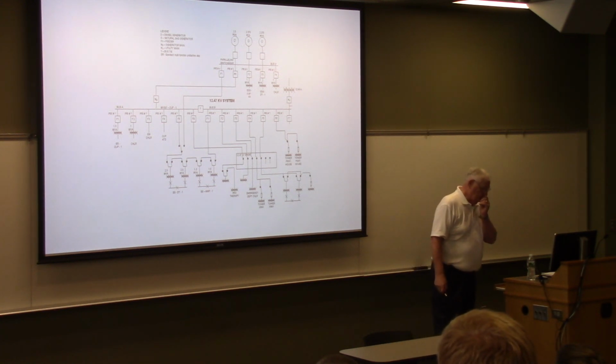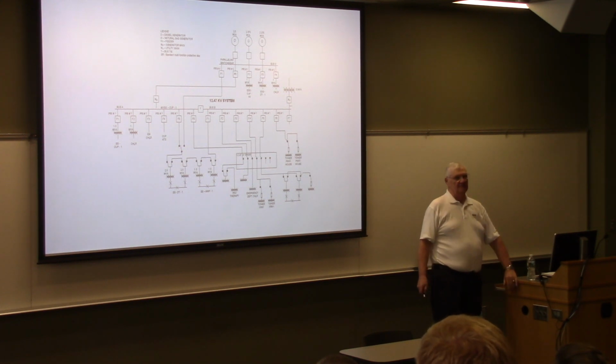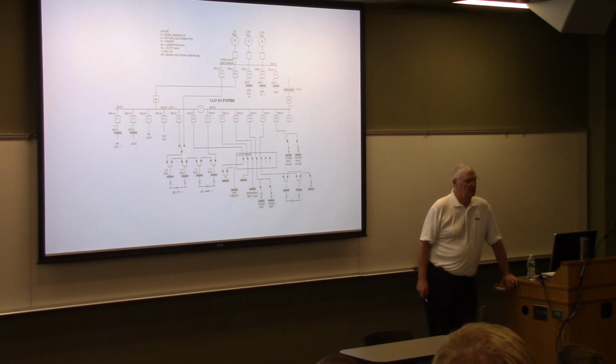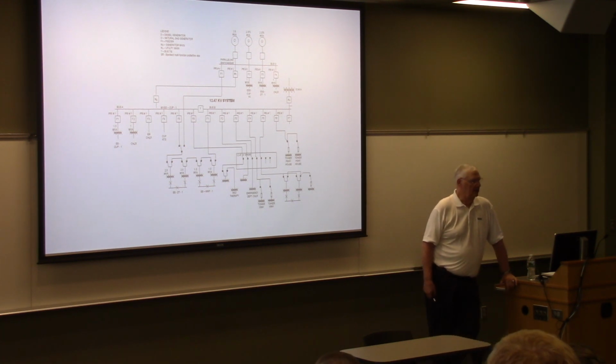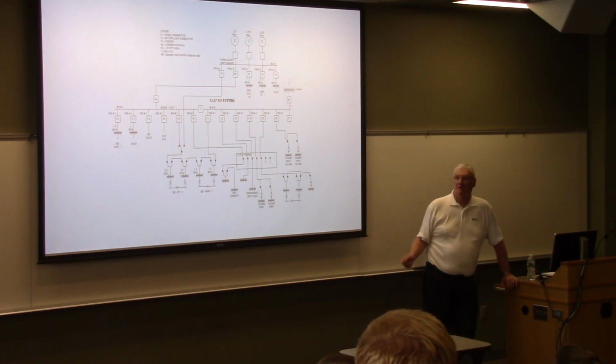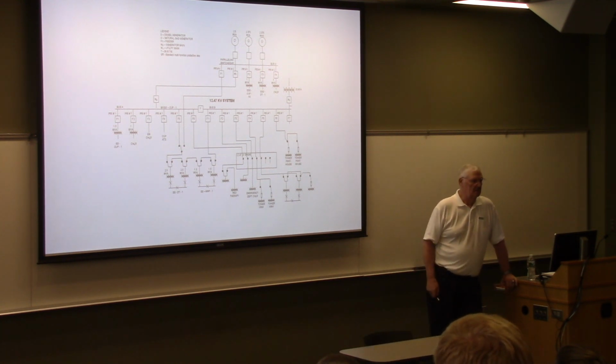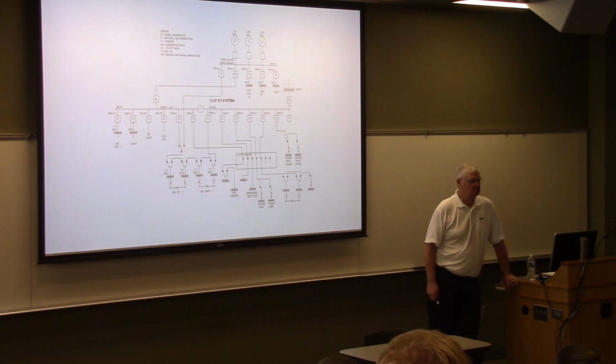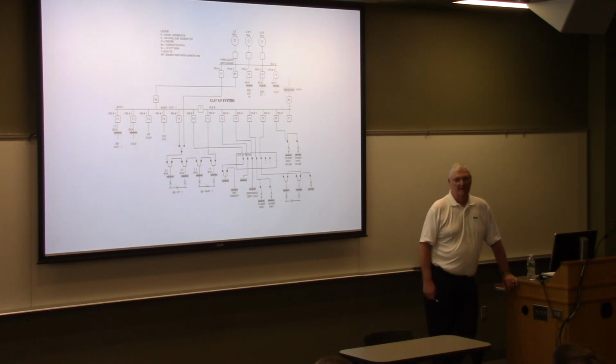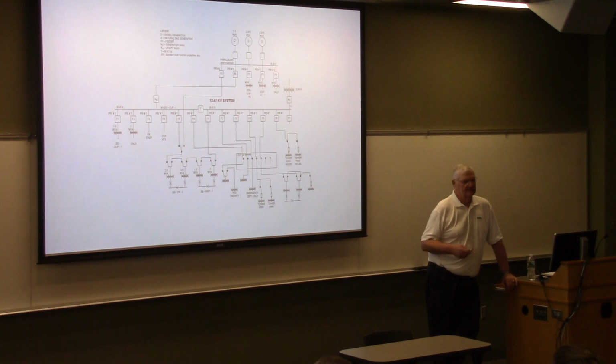generator bus. Now this system's been in operation for 3 or 4 years, and all of a sudden at 7:30 in the morning, their diesel starts up, they disconnect from the utility, 15 minutes later they reconnect to the utility and shut the diesel down. But they disconnected the gas generators too. And then the next day, Tuesday morning, 7:30 in the morning, they go through the same exercise. Wednesday morning, they go through the same exercise.